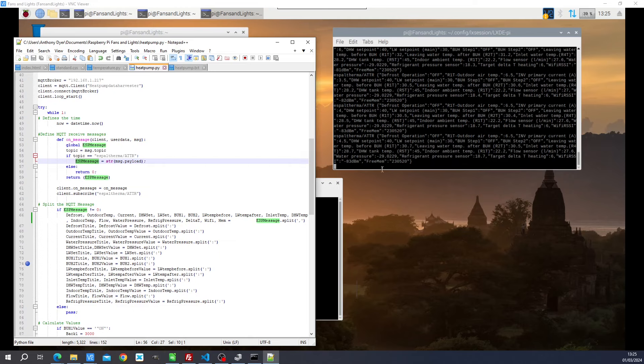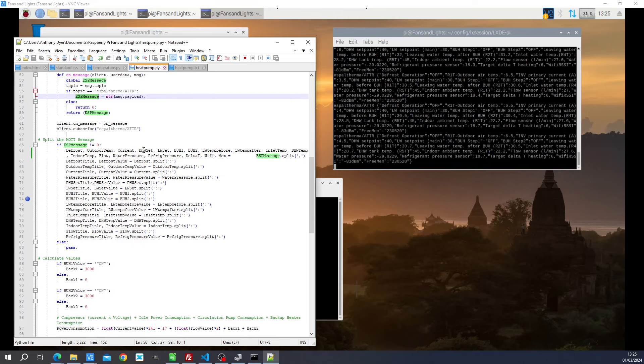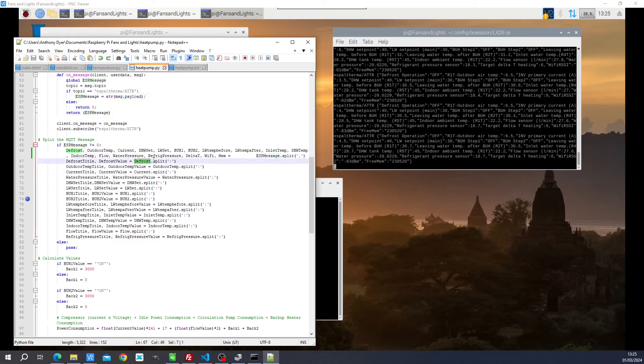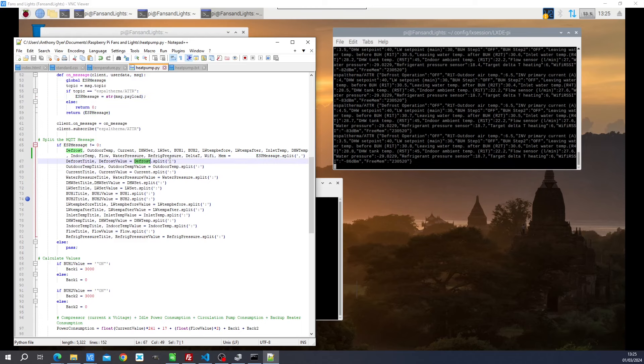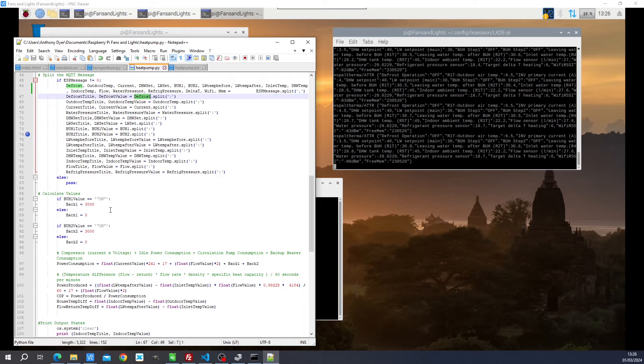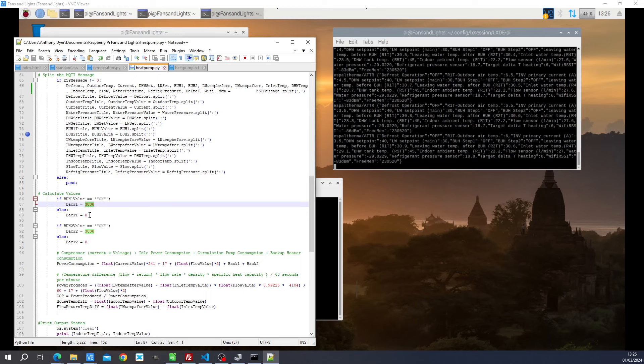So what do we do with this long message? Well, we split it. So we will define variables for each component of this message. And we will define a split using the comma. So as you can see, between each topic, we've got a comma. So we've got a comma between defrost operation and outdoor air temperature for example. So once we have got defrost as an example, we want to split it again. And this time we want to split it on a colon. So as you can see here, we've got the description on the left side of the colon. And we've got the state on the right side of the colon. So in this case, the defrost operation is off. And we do this for each topic of interest. Now, one of the things we will say is that if the backup heater is on, then we can assume that the power output is going to be 3000. There's no modulation on these resistive heaters at all. So it's either 3000 or it's zero. Same with the stage two backup heater. If it's on, it's 3000. If it's not on, it's equal to zero.